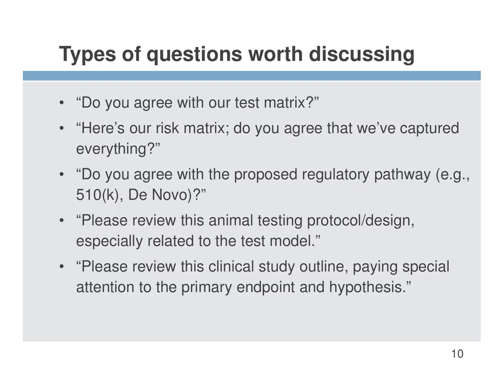So you want to have a pre-sub. What kind of questions? Now, some of these come from the guidance, some of them don't. But here's some of the typical questions that are worth discussing. Do you agree with our test matrix? Here's our risk matrix, FDA. Do you think we've captured everything in terms of risks? Do you agree with our regulatory pathway?